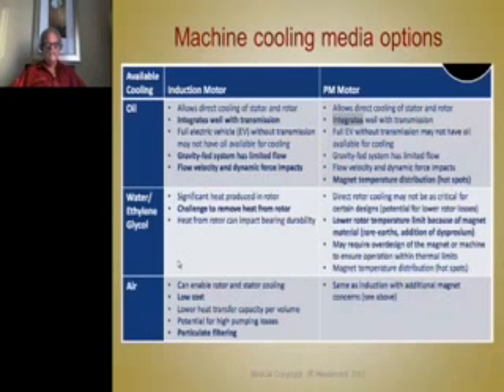And the way you can use that oil is in this cooling jacket around the outside that looks like the same one the water jacket uses, but you can also spray it directly onto the end turns of the stator winding if they're properly insulated, and onto the ends of an induction rotor.